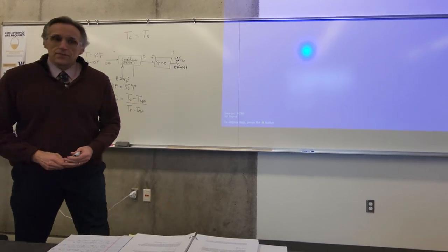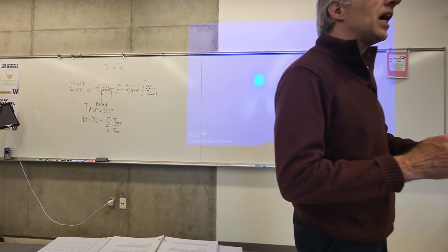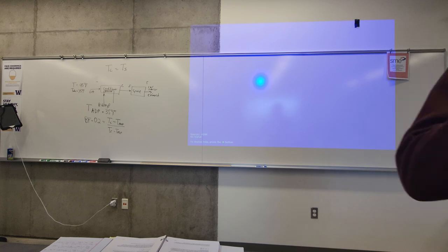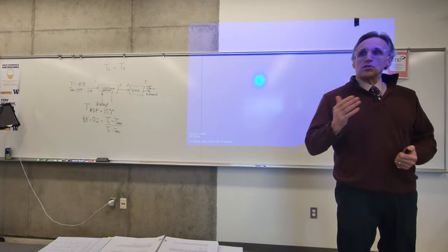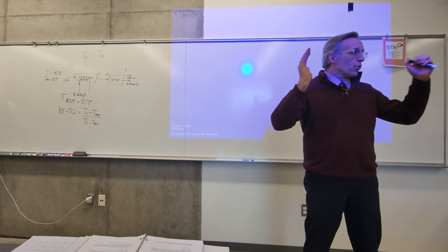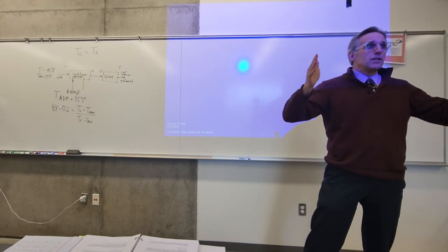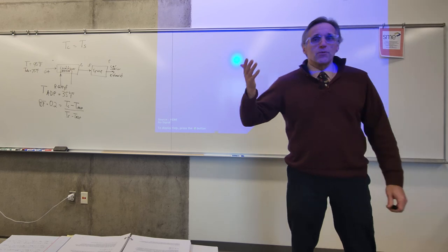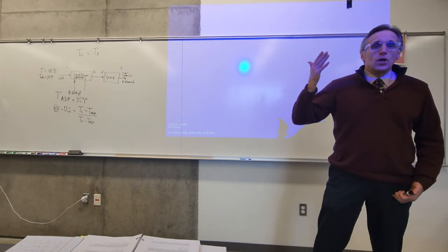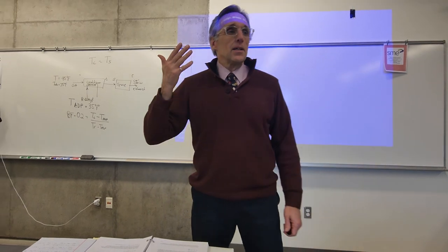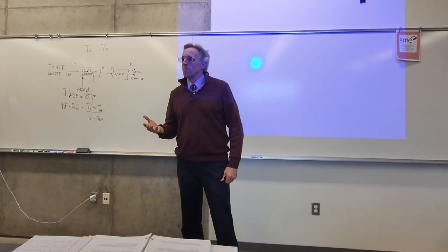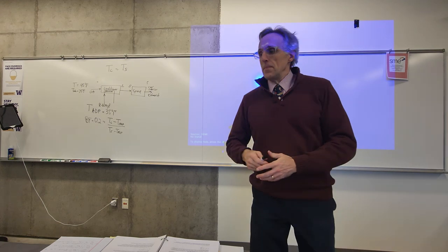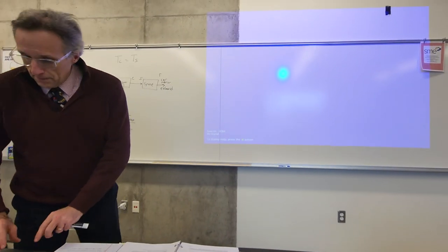Okay, let's take a look at this. We're coming at the HVAC design from the opposite side. Last time we were looking at the space, and we were designing our system given the space load, the heat transfer analysis on the room. So we had a sensible heat load and a latent heat load for the room. Now we're coming at it from the equipment side, because for the equipment there's also a sensible heat. We call that the equipment sensible heat capacity and the equipment latent heat capacity. Because we have to choose equipment that has a capacity that matches our space load.